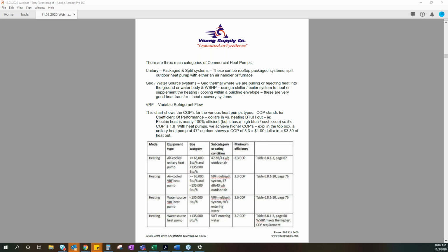So we're going to start out talking about the 3 main types of commercial heat pumps. There's a 4th one that we're going to get into towards the end. Unitary, this is what you're normally used to seeing. These are your rooftop units, your split system units. We're seeing a trend now towards heat pumps with gas heat furnaces. This has become very popular on the grow room side of the business. We're seeing more heat pump applications going into the grow facilities in Michigan.